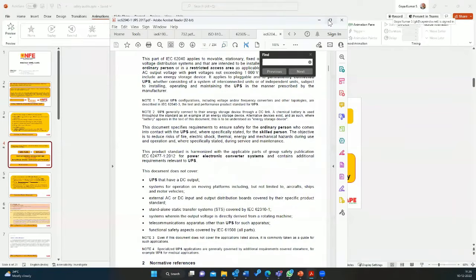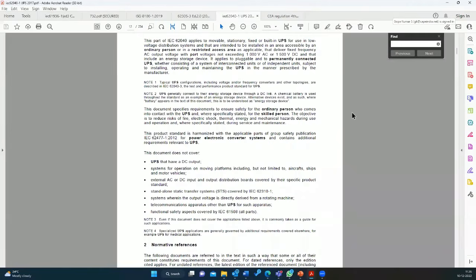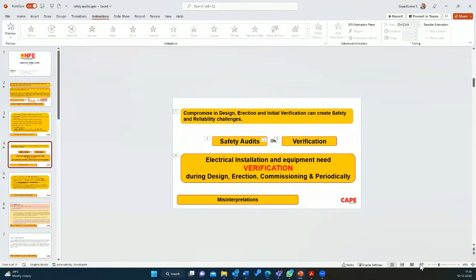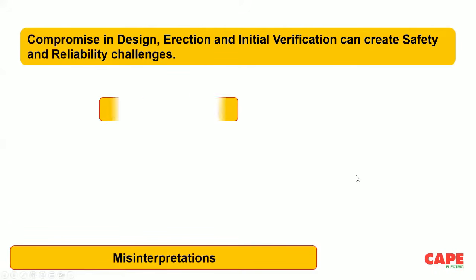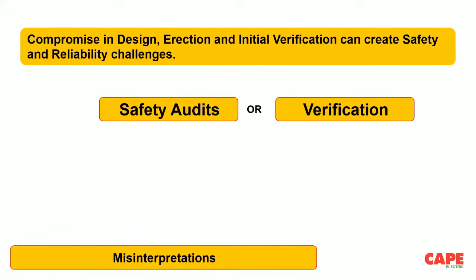I am also showing you a standard about UPS. Let us search the word audit. No word called audit. Verification is used 13 times in this particular standard. So basically what I wanted to tell you is the word audit is actually not applicable for an electrical installation. Instead, what we have to do is verification. Audit is a sampling process. A chartered accountant makes an audit. He doesn't go through the entire accounts. He checks on a sampling basis.